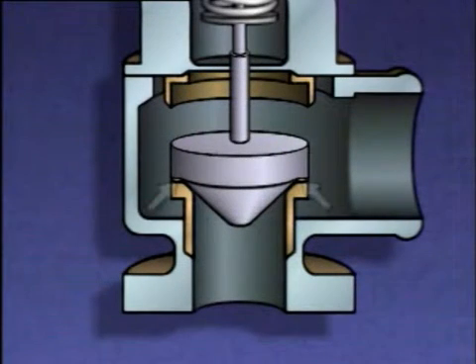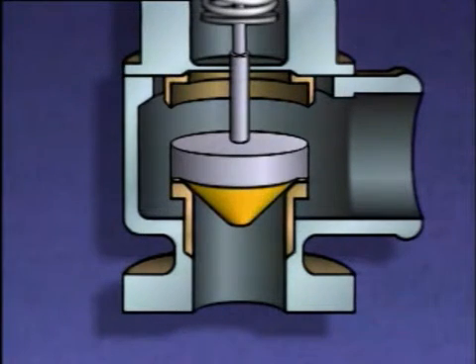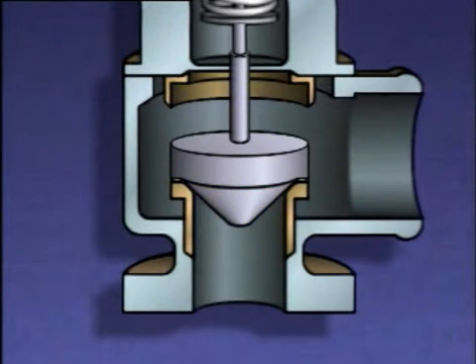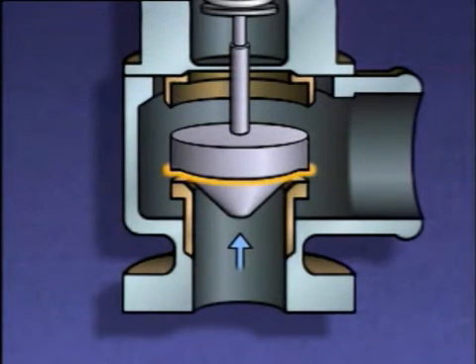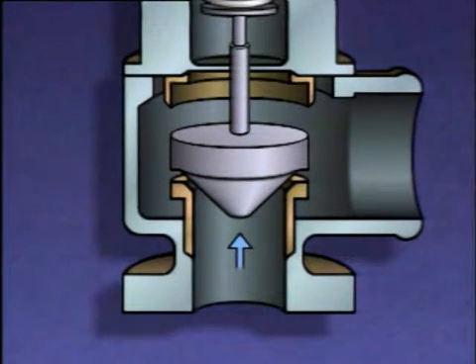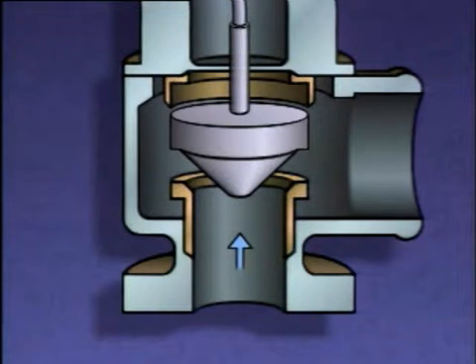The disc of a safety valve has a lip that isn't exposed to system pressure when the valve is closed. The center portion of the disc is always exposed to system pressure. If the valve is set to open or lift when the system pressure reaches a preset limit, say 200 PSI, the disc will start to lift when that pressure is reached. When this happens, the lip of the disc is suddenly exposed to system pressure as well. And since a larger area of the disc is now exposed to system pressure, there's more force exerted on the bottom of the disc. This increased force overcomes the force exerted by the spring and causes the disc to pop open to about a 60% open position.